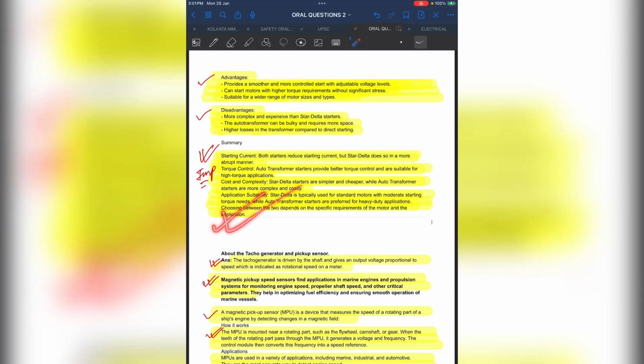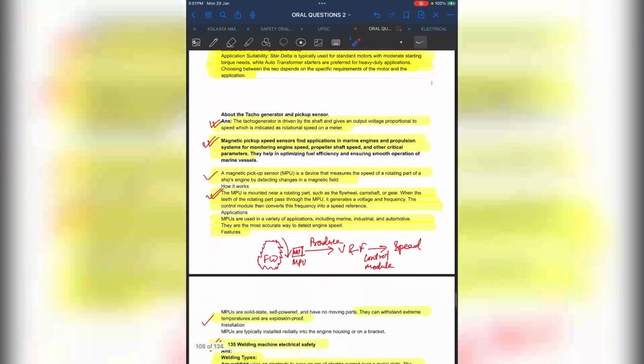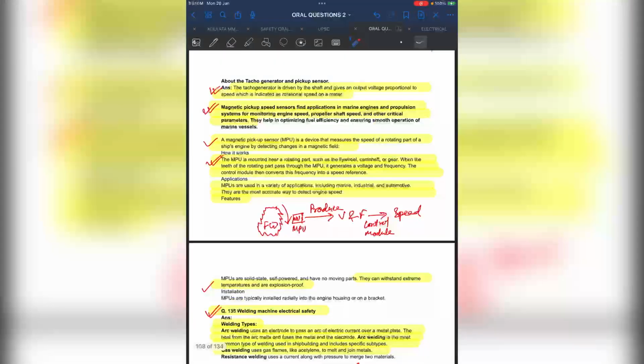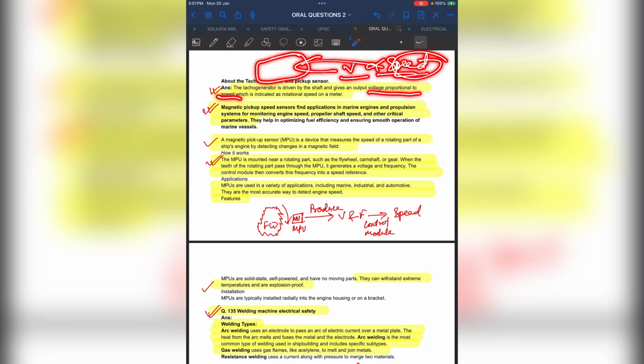So these are the basic things about the tacho generator and pickup sensors. With the tacho generator, we measure the speed and RPM. The tacho generator is driven by a shaft and gives an output voltage proportional to the speed, which is indicated as the rotational speed on a meter. The output voltage is directly proportional to the speed. Whatever voltage is provided by the tachometer is converted into a speed, and this speed is shown on the meter of the tachometer.